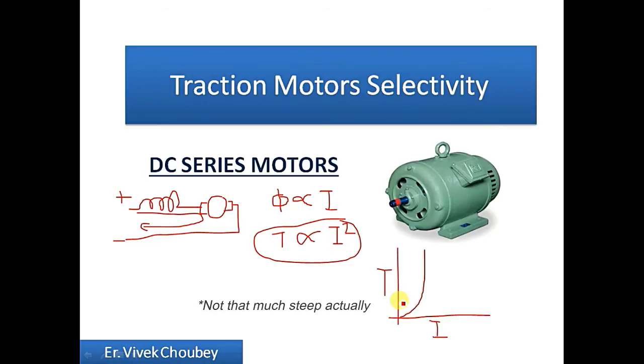The second thing about this: from the relation we can see the torque is directly proportional to the square of the current, which means it doesn't depend on the polarity of current. So even if I supply it with an AC voltage, I will be getting the same unidirectional torque, the positive torque.